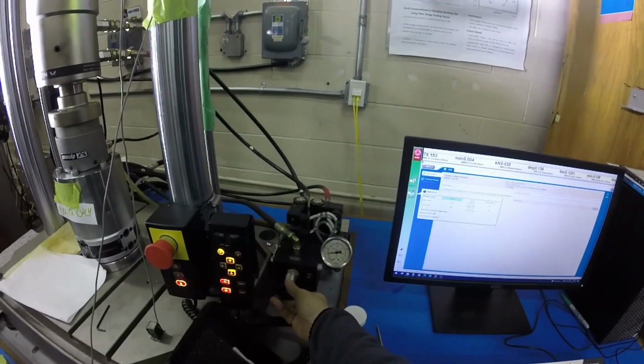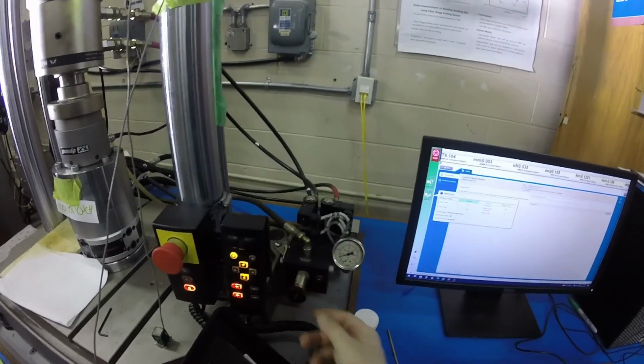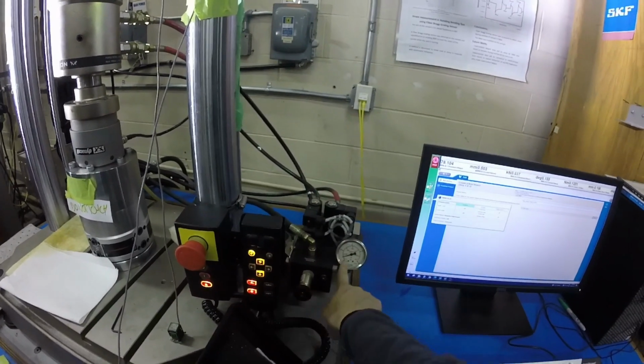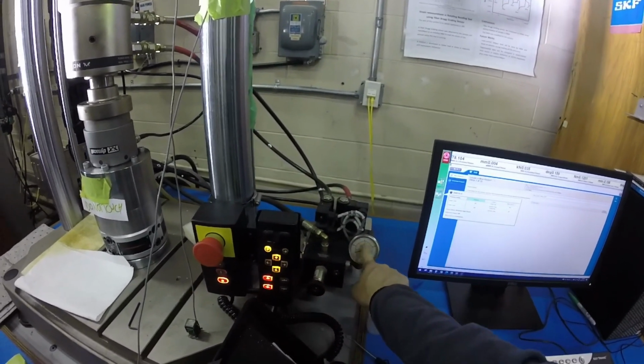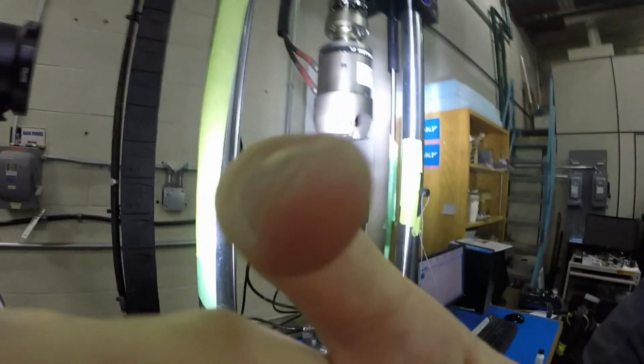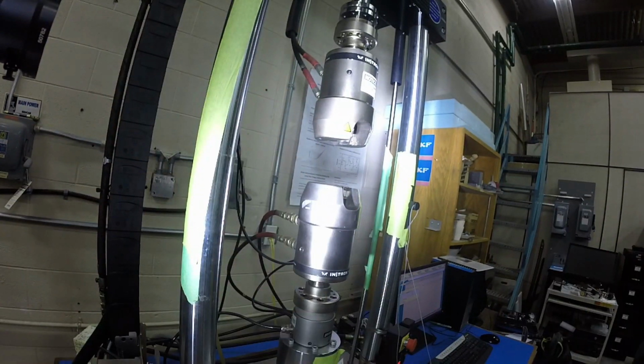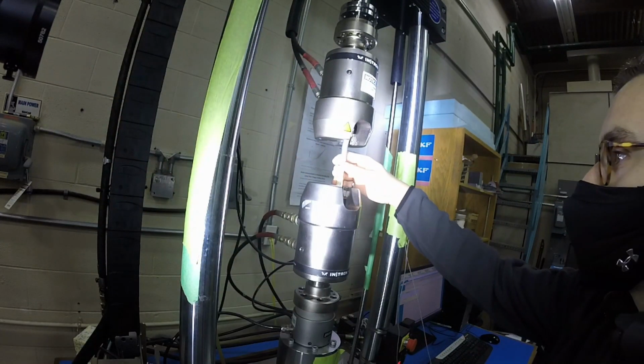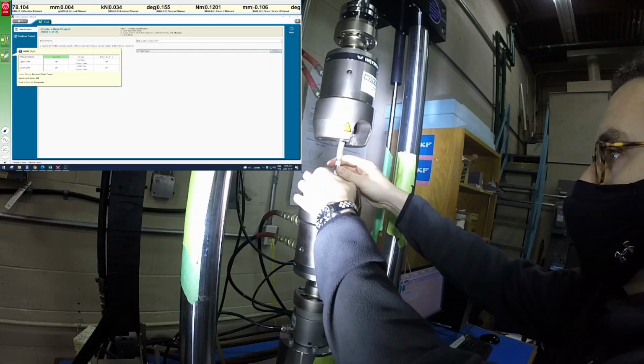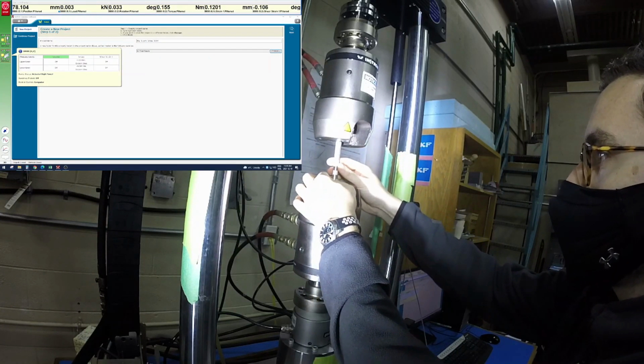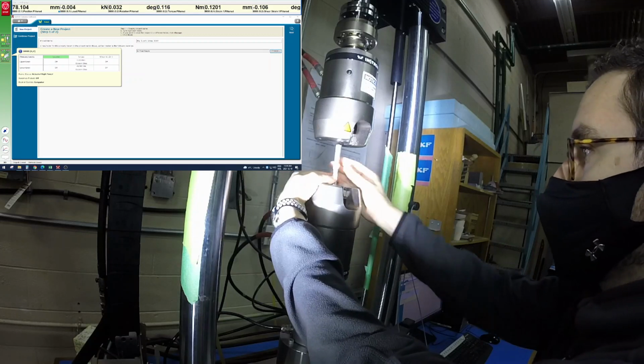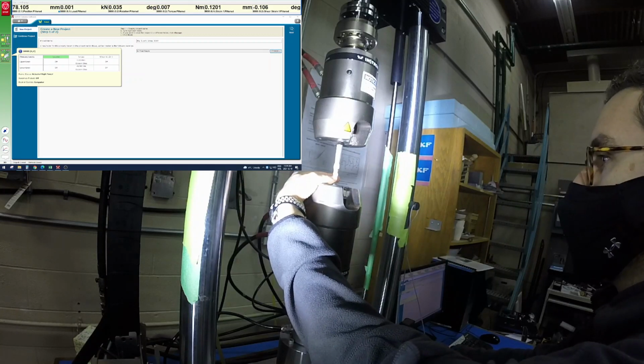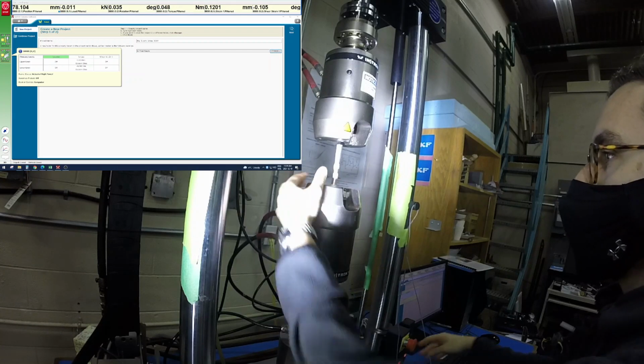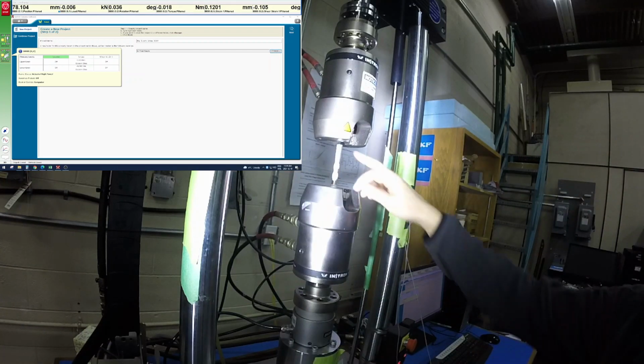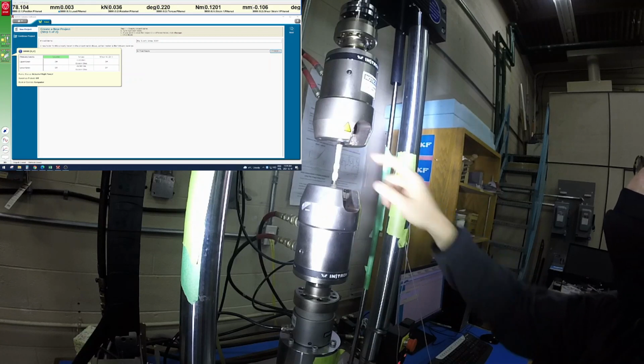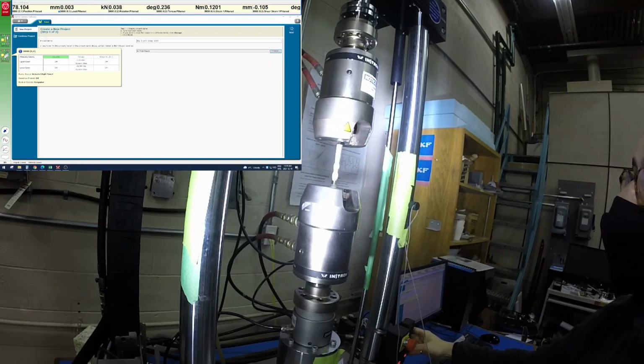To adjust the pressure on the hydraulic grips to suit your specimen, there is an adjustment knob here on the right hand side that allows you to change the pressure to suit whatever clamp load you need. So we'll go ahead and clamp the specimen into the grips, and you shall roughly line it up with where you want, and then click clamp on the lower clamp. And then now you can see obviously there's a gap between the upper grip and the top of the sample, so we're going to want to move this down.